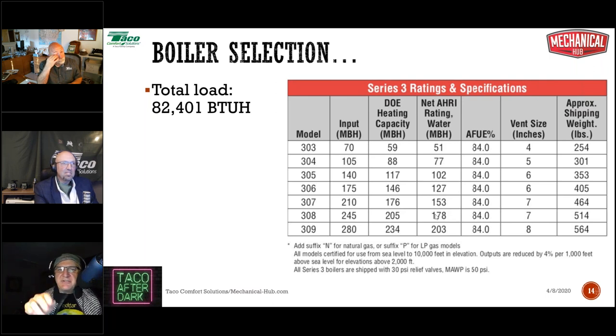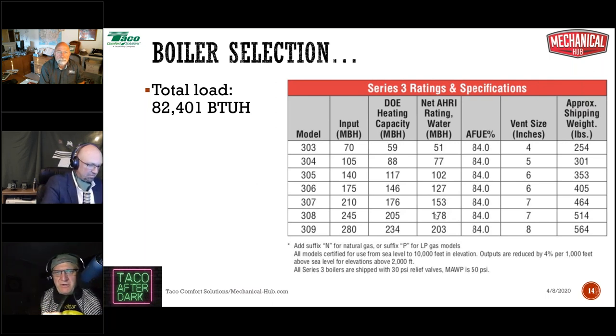If you look at the next two columns, you have the DOE heating capacity, and then the next column is the net AHRI, or in some cases, the net IBR rating. So you have two output columns. You've got one input column, and you get two output columns. How can one boiler have two outputs? That's cray-cray, as my daughter would say. This is nuts. How do you do that? And which one do you use? All right. If we went strict DOE, we could certainly use that 304, because DOE heating capacity is 88,000. But if we look at the net AHRI, it's 77,000.